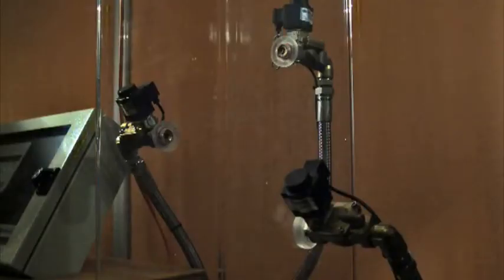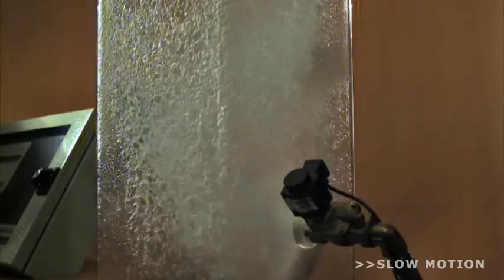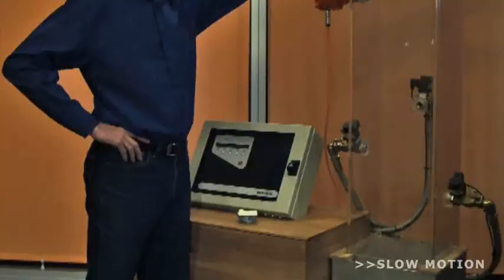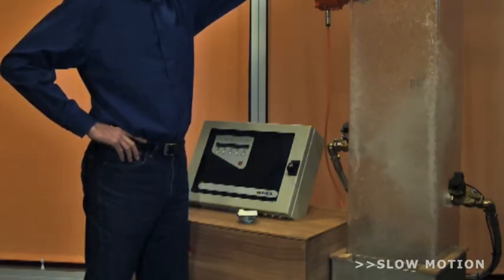Firefly always uses a minimum of 3 water nozzles from different directions to penetrate the material flow and ensure coverage of the entire cross-section inside the process duct or chute. Spraying water from only one side will leave uncovered sections inside the process duct or chute.